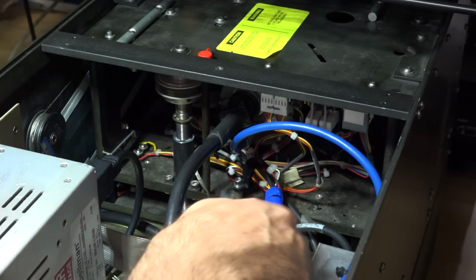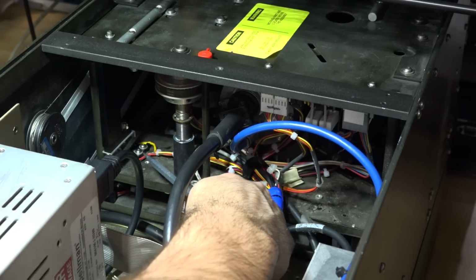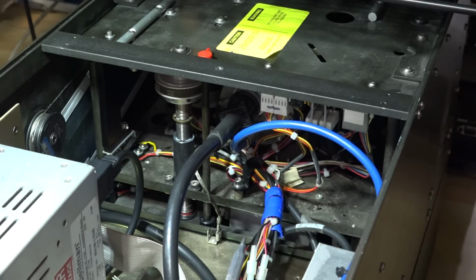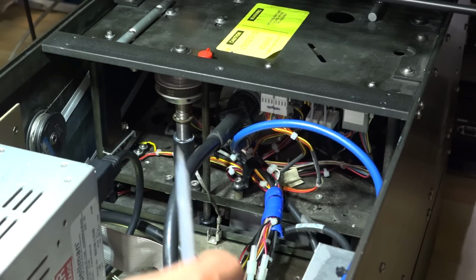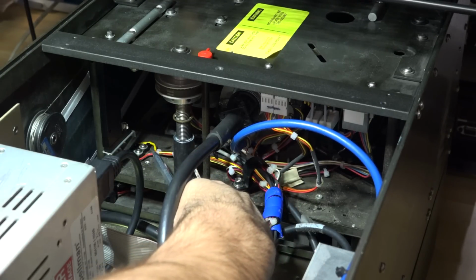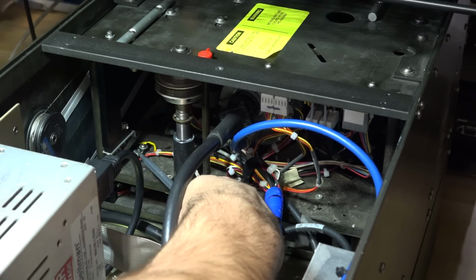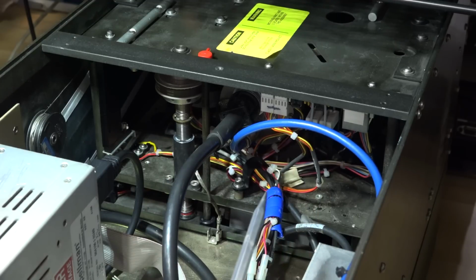And that wasn't the first place I would have looked. It looks like those photodetectors fail over time when they have a reverse bias voltage on them and the transmitters are not on, and I think they just have failed over time. So I opened them and removed them and replaced the detectors. You can see the wire looks a little bit different. I couldn't find an exact replacement, so that was some work for sure to be done.